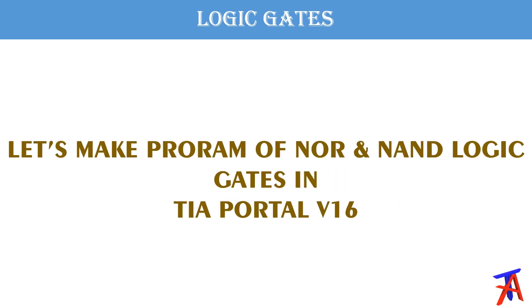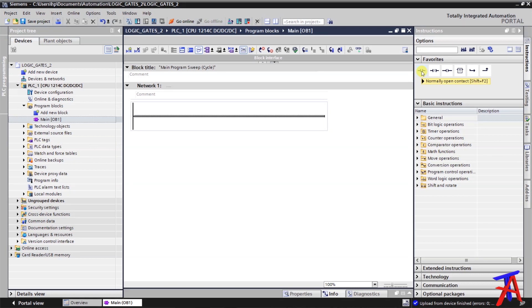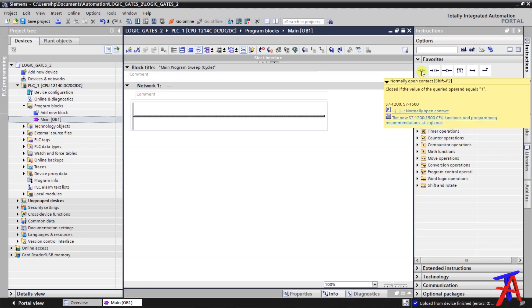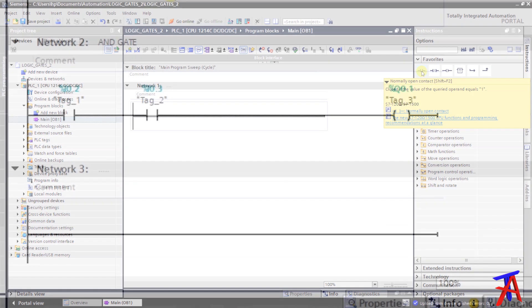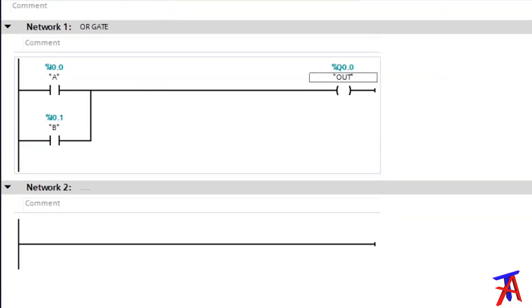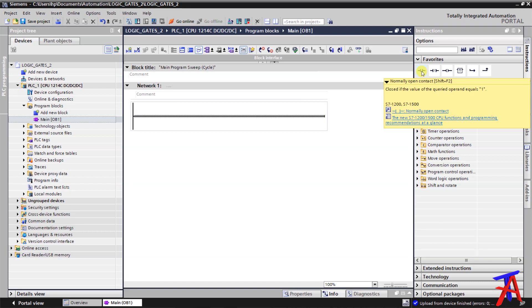Let's make these logics in TIA Portal version 16. To make the logic we should know some basic things: if we have to make logic in multiplication like a dot b, which is AND gate, we add the logic in series. And if we have to make logic like a plus b, which is OR gate, we add the logic in parallel. This was shown in my previous video — I'm adding the link in the description. And the last thing is: for complement of the logic, we will add an NC button.